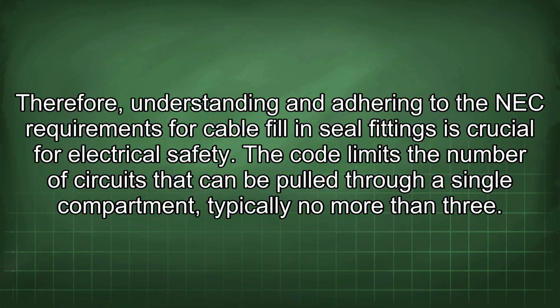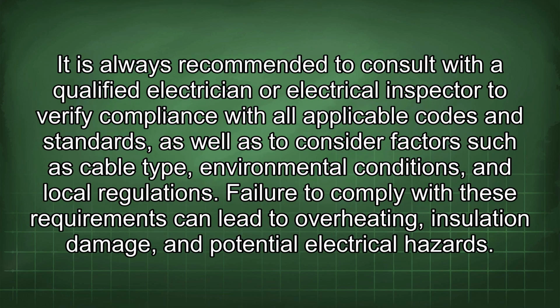electrical safety. The code limits the number of circuits that can be pulled through a single compartment, typically no more than 3. It is always recommended to consult with a qualified electrician or electrical inspector to verify compliance with all applicable codes and standards, as well as to consider factors such as cable type, environmental conditions, and local regulations. Failure to comply with these requirements can lead to overheating, insulation damage, and potential electrical hazards.